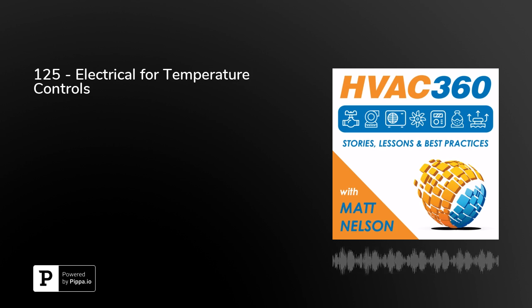The downside was that if you used it for certain things like motors and relays or some other noisy power supplies, you could get a situation where the signal wasn't real great. And they were also susceptible to voltage drops over long distances. Again, you realize, when we talked about the difference between AC and DC in the power distribution system, you notice that the one downside to the DC system was the distance. You'd have to have a generator station every mile to be able to get it to the local houses, whereas an AC system could go much, much farther. The same thing holds true when we're using DC voltage on the control side.